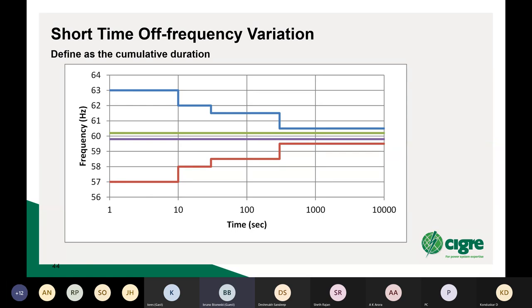Similarly on off frequency, the two lines in the center of the figure are plus or minus some value around your nominal frequency, which can be 50 or 60. We've shown 60 in this case, but it's also applicable for 50 hertz. And then again, the requirements for off-frequency operation can affect equipment ratings, particularly filter ratings. And generally, it's not enough to just, even a curve like this can be easily misinterpreted in a spec.